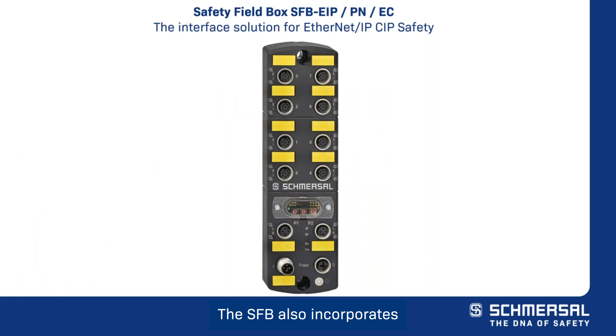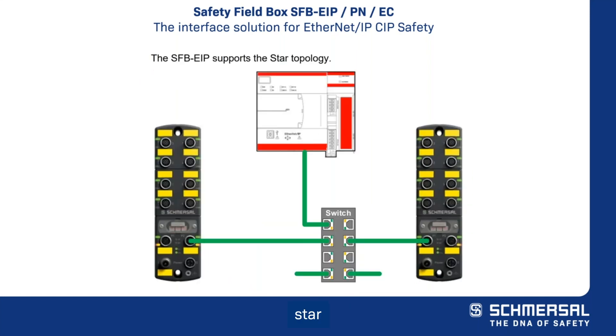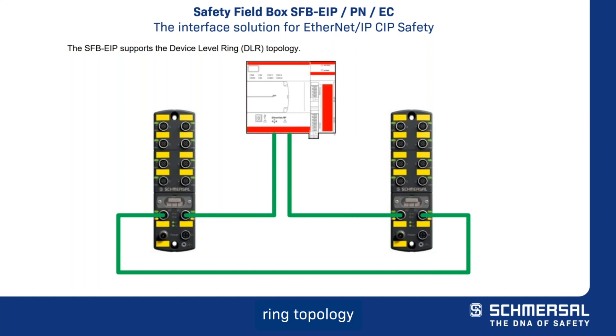The safety field box also incorporates a dual port Ethernet IP switch for the implementation of up to 10 safety field boxes in a linear, DLR, or device level ring topology that best supports your application. A device level ring network provides you with the resilience of a single fault tolerant network with media redundancy and fast network fault detection and reconfiguration.